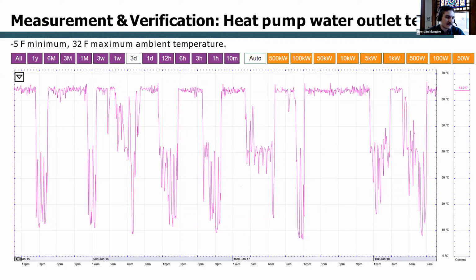This is just a screenshot from our eGauge data. It just shows that it was -5°F out for a couple of these times, and it shows that we're producing our target temperature even when it's -5 out. This is just 63 degrees Celsius. This is water being sent from the heat pumps back to the storage tanks.